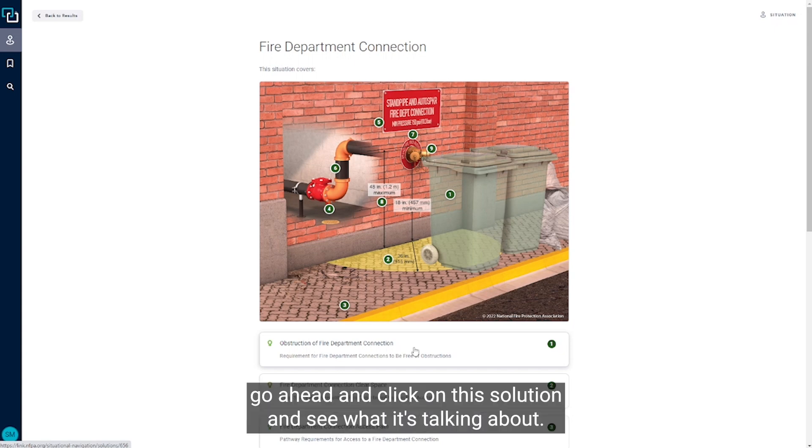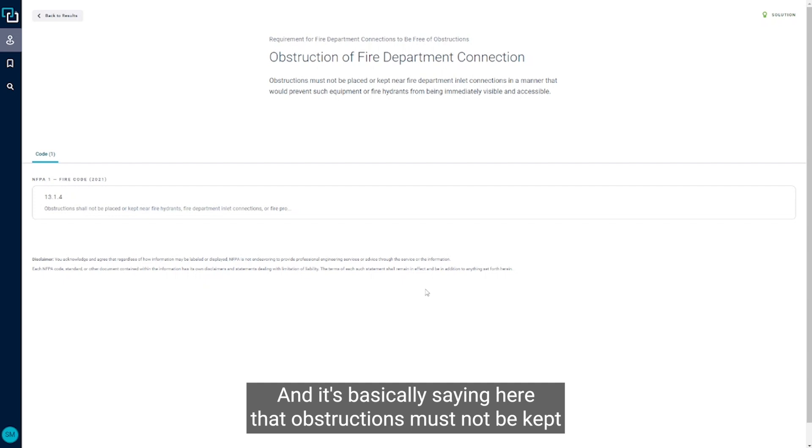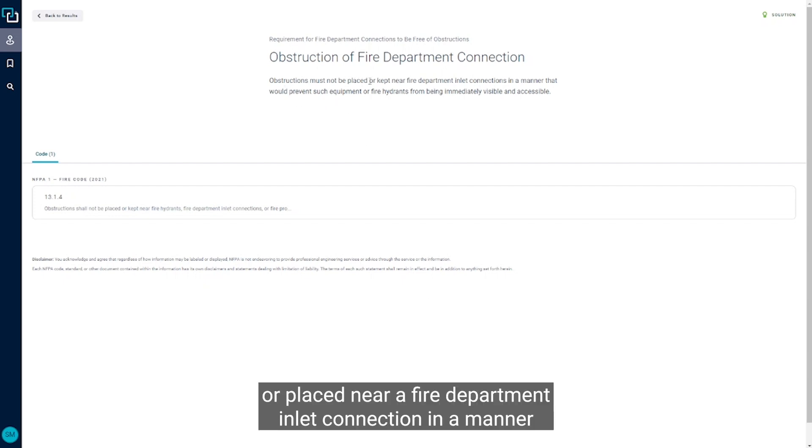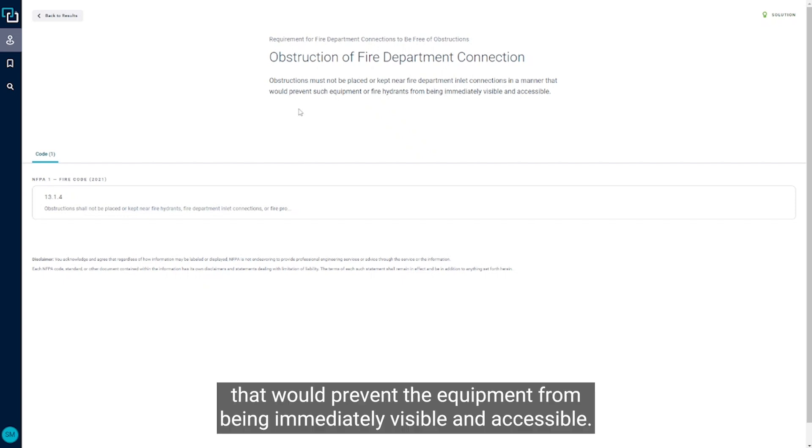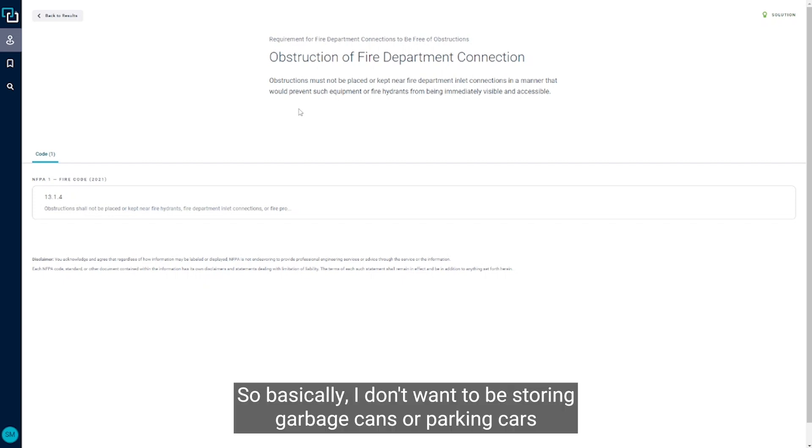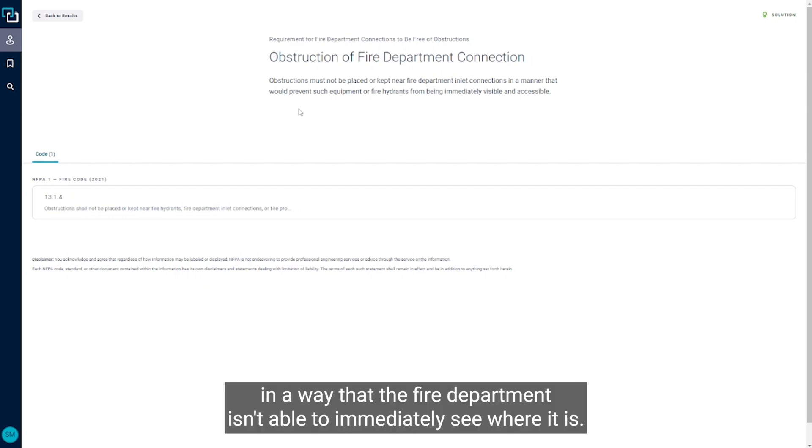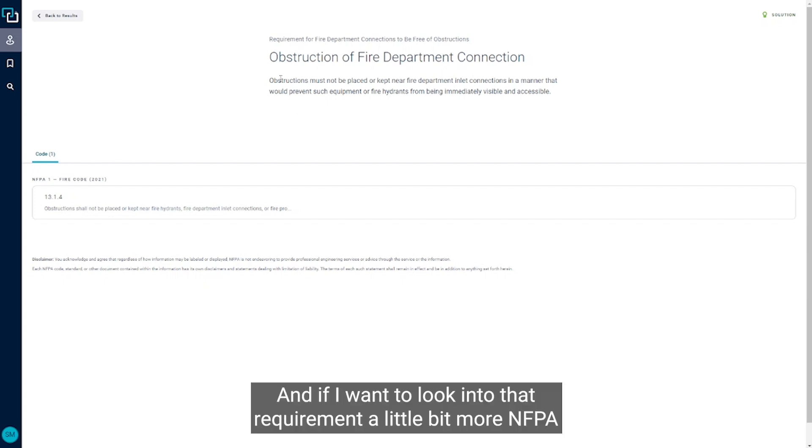So let's go ahead and click on this solution and see what it's talking about. It's basically saying here that obstructions must not be kept or placed near a fire department inlet connection in a manner that would prevent the equipment from being immediately visible and accessible. So basically I don't want to be storing garbage cans or parking cars in front of the fire department connections in a way that the fire department isn't able to immediately see where it is.